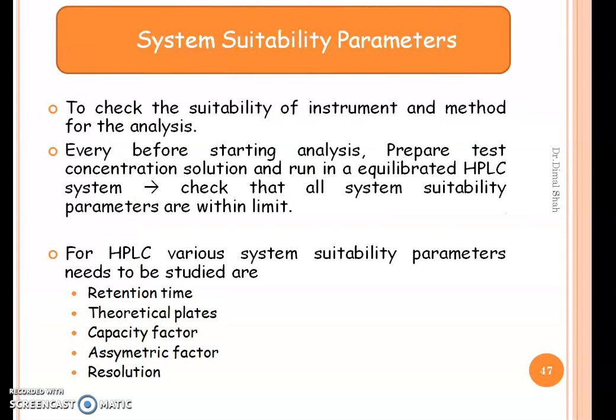After completing the validation parameters, let us move to the system suitability parameters. To check the suitability of the instrument and the method for analysis, a system suitability test has to be carried out. Every day before starting analysis, prepare the test concentration solution and run it in an equilibrated HPLC system. The system suitability parameters for an HPLC method are: retention time, theoretical plates, capacity factor, asymmetric factor, and resolution.